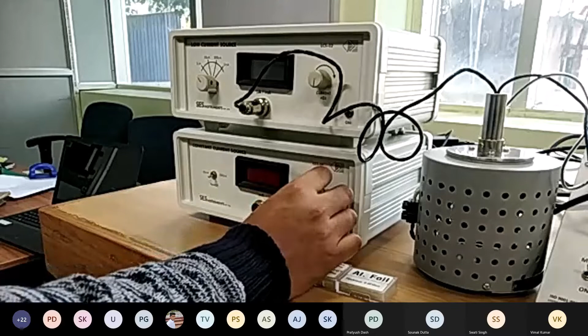This is the constant current source. Here the range is up to 20 microampere, from 0, and there's also a higher range up to 200 milliampere. We select the range using this selector. If we select this one, it moves up to 20 milliampere; beyond that, if we need more current, we switch the selector to the other range, 200 milliampere, and then the display shows milliampere instead of microampere. Here is the knob to adjust and increase the current within that range.